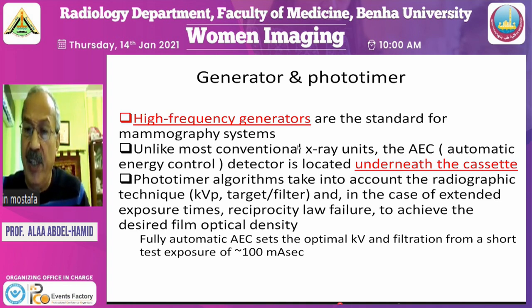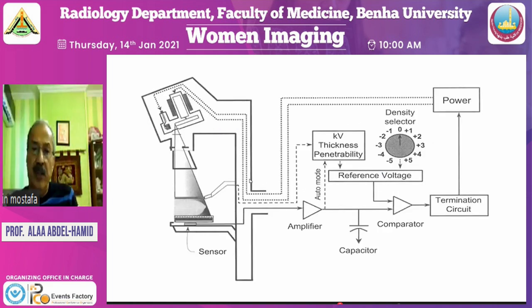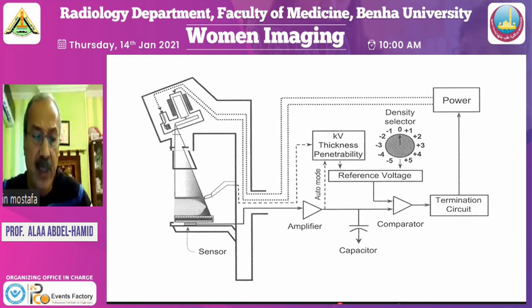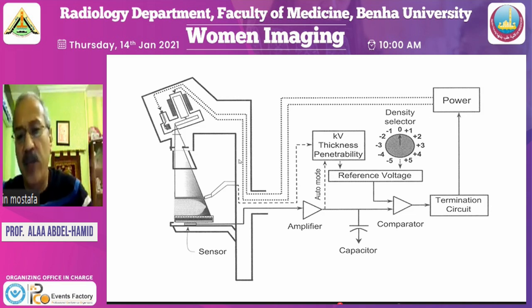We have to use high frequency generators with the use of automatic energy control underneath the cassette. This is the design of the machine. Here, the X-ray tube, the collimator is present here, the sensor is present behind. First, we initiate or start by small dose of X-ray that passes through the breast, measured by the sensor, and then a feedback circuit is going to the machine in order to auto monitor or also select the density, the amount of X-ray, control the kilovolt and the milliampere second, and then we get the image.